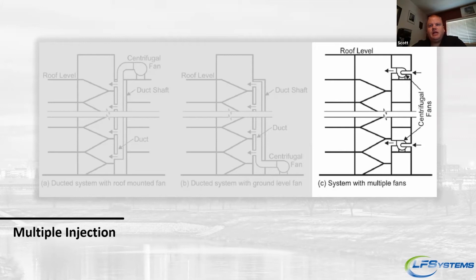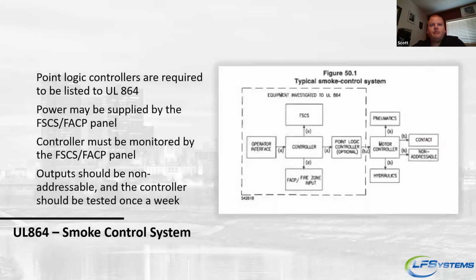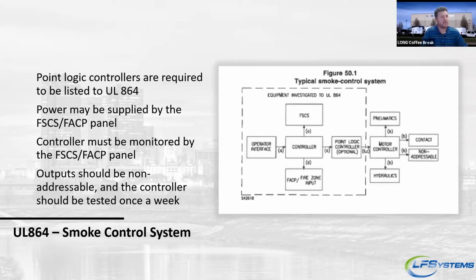Everything you've seen up to now, you're probably very familiar with, but let's take a look at how we control these. Everything within the dotted line here needs to be UL 864 listed. That includes your FSCS, your FACP, your controllers, your operating interface, and also your point logic controller. Any controller that controls the VFD, fans, dampers, things of that nature is considered a point logic controller and should be UL listed.